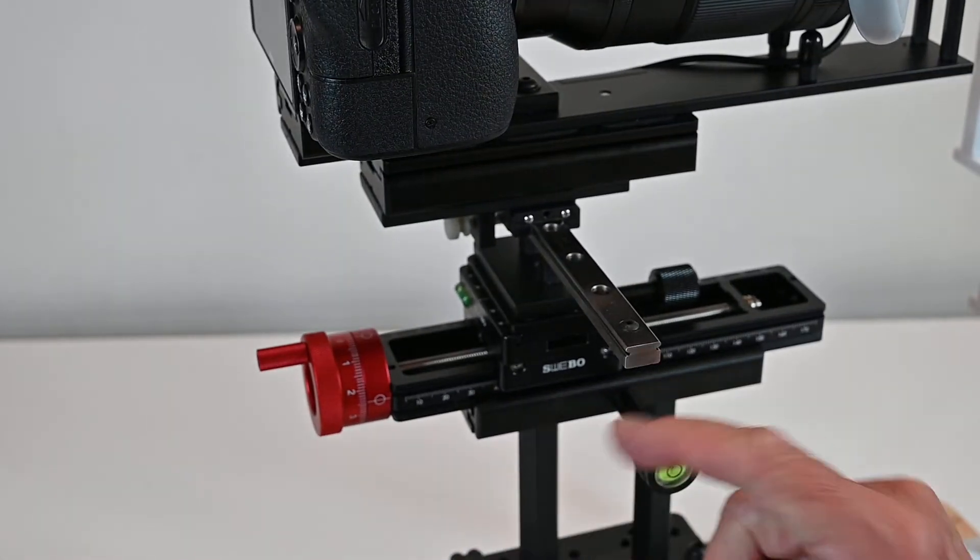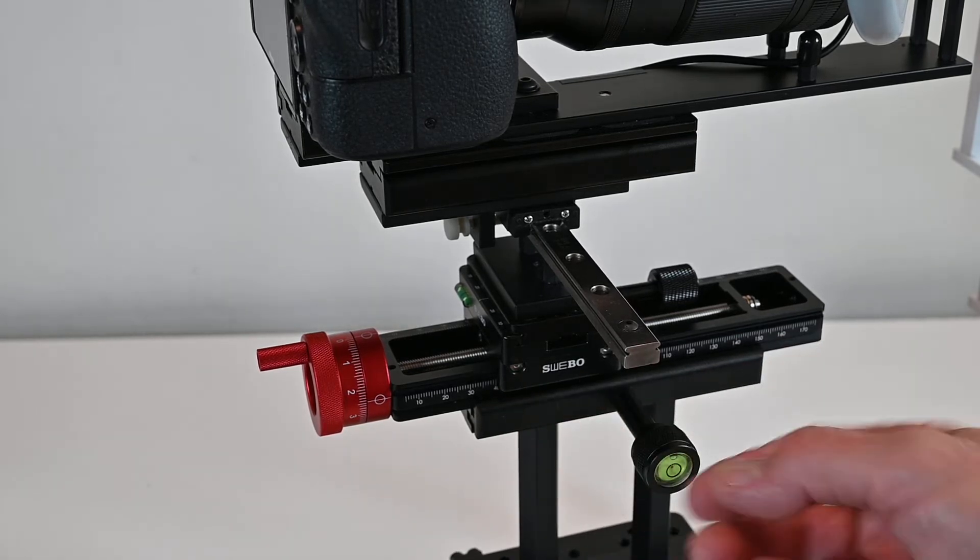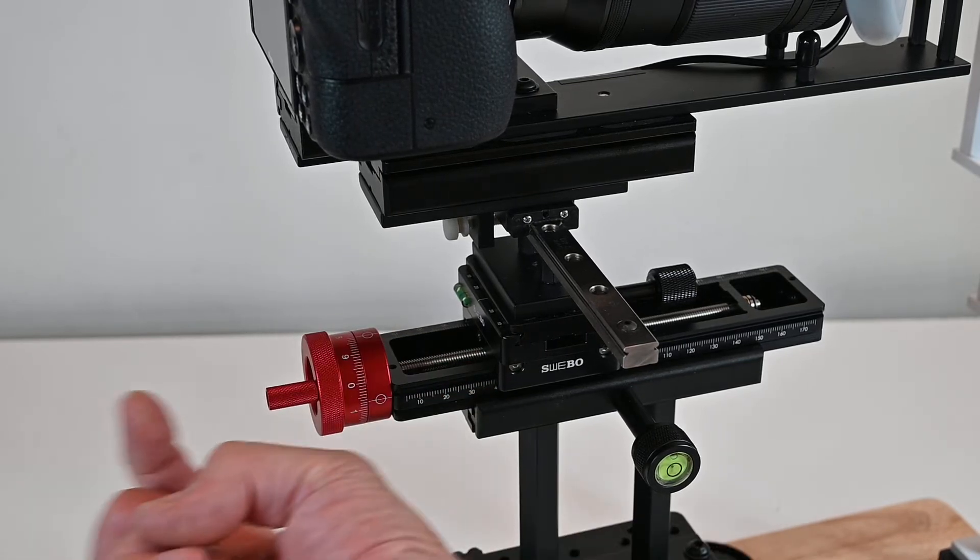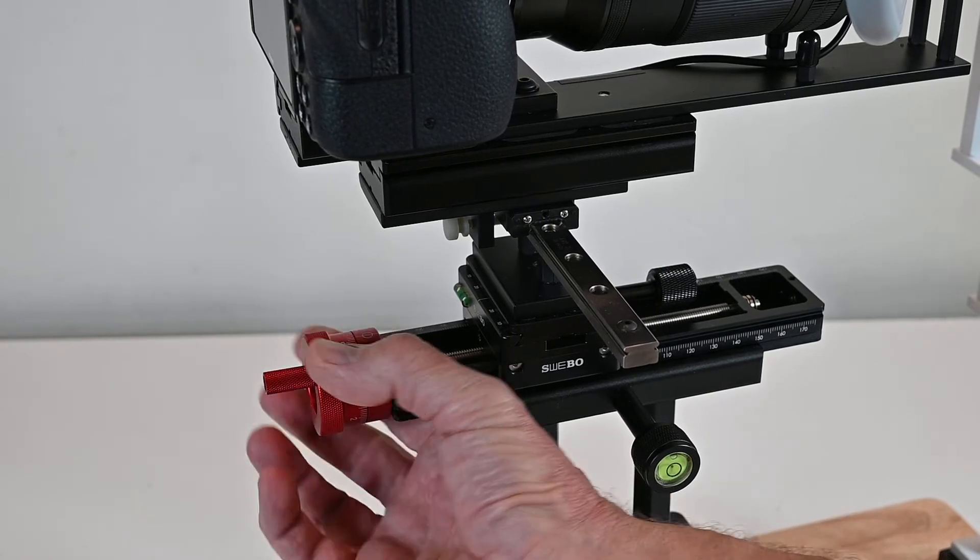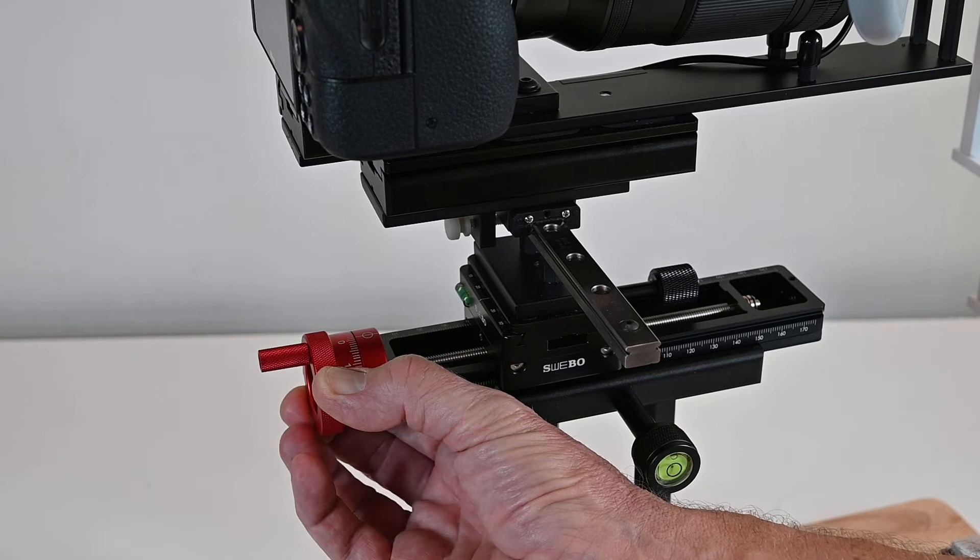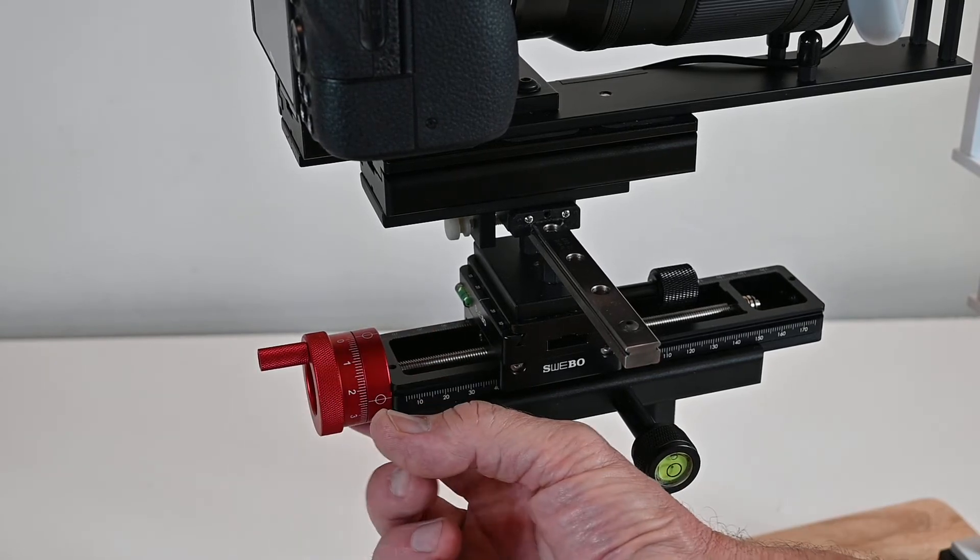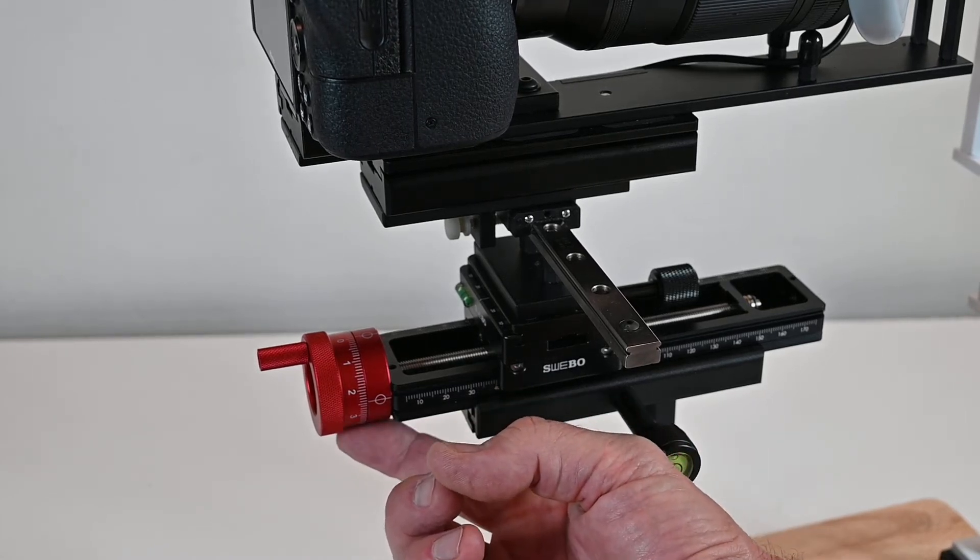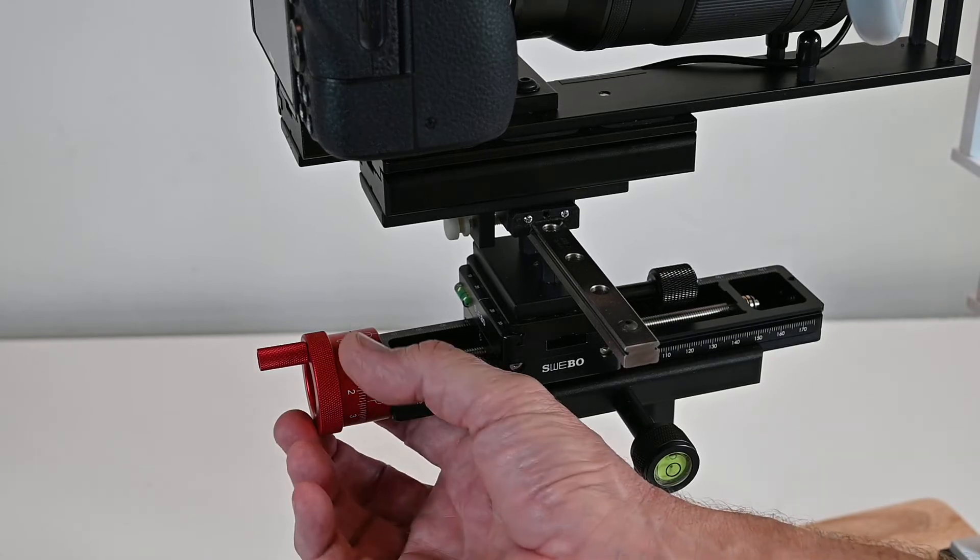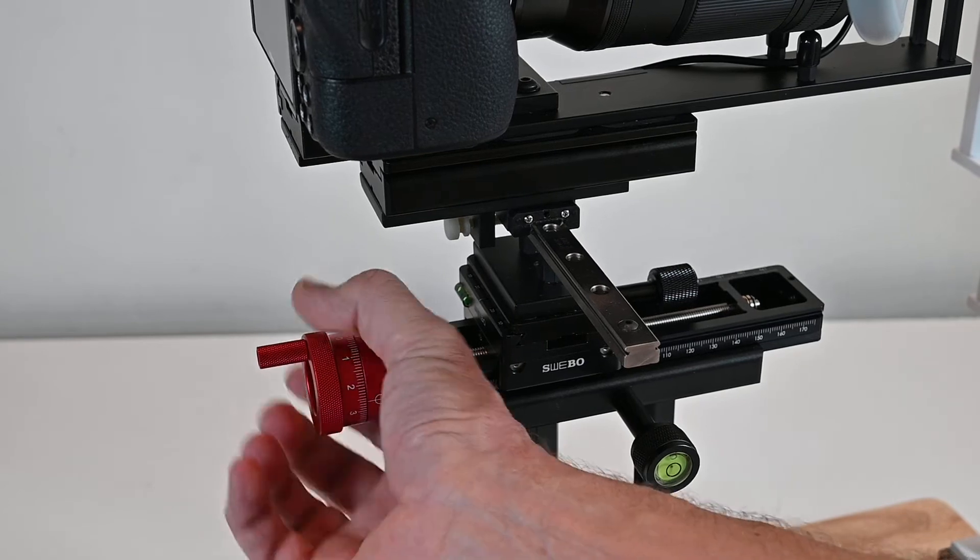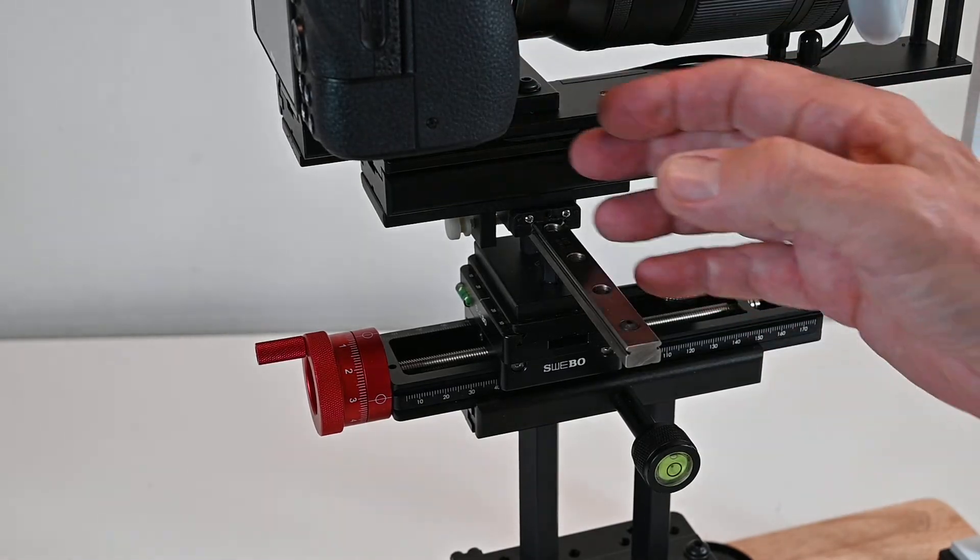As for the position, for most people you'll want it right on the 40 millimeter point, plus or minus a couple millimeters. When you turn this, if you turn it clockwise from the operator's standpoint, clockwise will bring it back and counterclockwise will bring it forward. There is a scale on here for hundredths of a turn. Each turn on this one is a fast, relatively fast travel, so each turn moves it four millimeters. Since every iris is going to be within a couple millimeters from the camera, you generally don't have to turn it more than a turn each way to cover everybody.